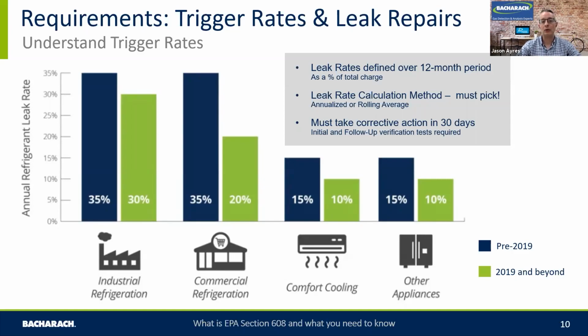Most people we deal with use the rolling average leak rate to calculate their current leak rate of the system. And every time you add refrigerant to the system, you must calculate that leak rate at that point in time. Because if you have a high leak rate, or it goes above what we term a trigger rate, I'll touch on that in a second, you have to then follow up with additional corrective actions to identify and try and ensure that any further refrigerant losses are mitigated. So what do we mean by a trigger rate? So a trigger rate is basically a level that if you go over it, so that's a percentage of your leak rate, you have to do additional checks on the system, and they're called leak inspections.